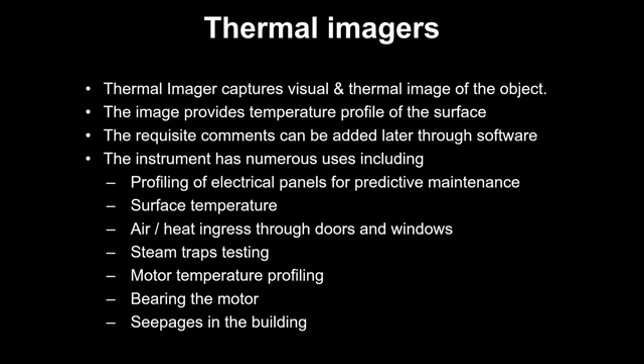You can do a lot of editing. It is very extensively used for all kinds of applications. Electrical panel, that's how it all started. So you can do it for electrical panel. You can measure surface temperature. We are doing that now. All pipeline measurements, cold pipeline, hot pipeline, any pipeline, furnaces, we do that. Here again, there are ranges. We have one up to 150 degrees, another up to 250 degrees, third one up to 600 degrees. So those are the thermal imagers we have, and we use them in different areas.